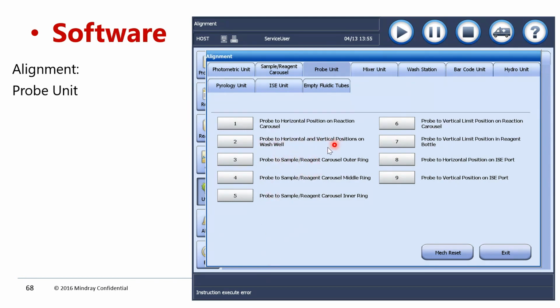So probe wash well vertical position, sample to reagent carousel outer ring, middle ring, inner ring, and probe vertical limit position reaction carousel. At the reaction carousel, your probe has to be at a certain height. You have to verify there is a tool. Probe vertical limit position on the reagent bottle. So suppose the customer is saying a lot more volume of reagent is left in the bottle, and he is not getting sufficient tests. You need to verify this vertical limit position on the bottle.